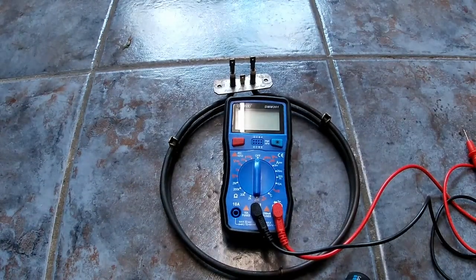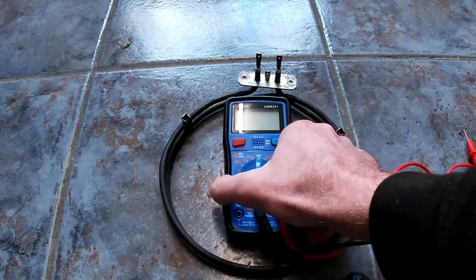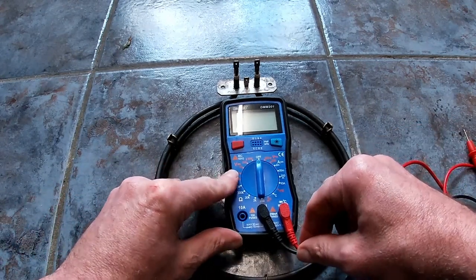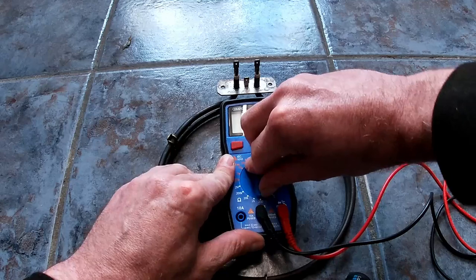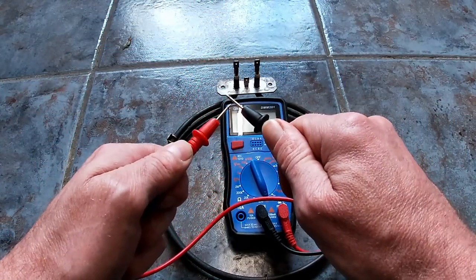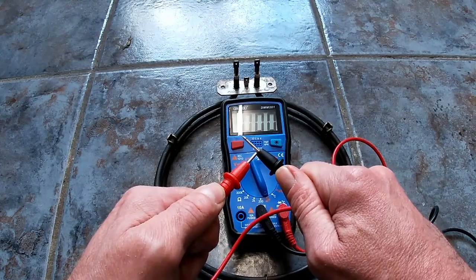Okay guys, so we've got the element out. I've inspected it. There's no obvious signs of any external damage. So we'll give it a continuity test with a multimeter. Now this multimeter has an audible setting for continuity. So we'll just test that, we'll test the reading, make sure everything's fine.